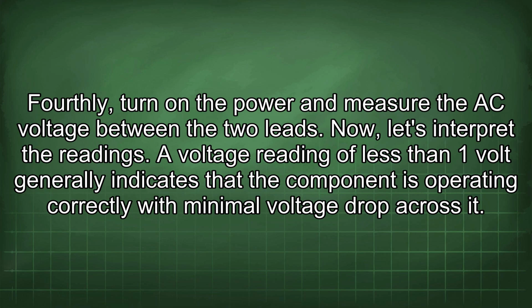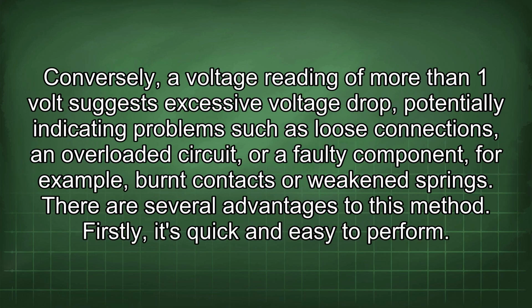A voltage reading of less than 1 volt generally indicates that the component is operating correctly with minimal voltage drop across it. Conversely, a voltage reading of more than 1 volt suggests excessive voltage drop, potentially indicating problems such as loose connections, an overloaded circuit, or a faulty component, for example, burnt contacts or weakened springs.